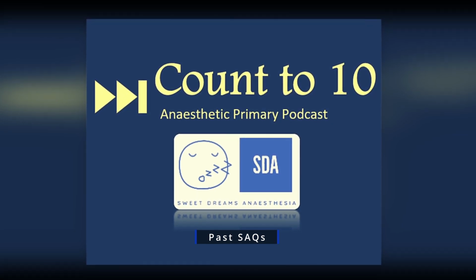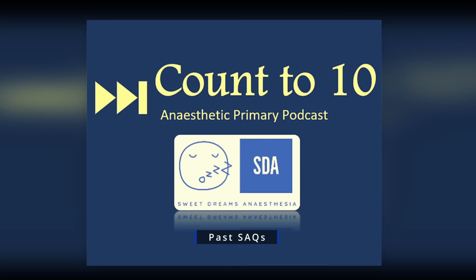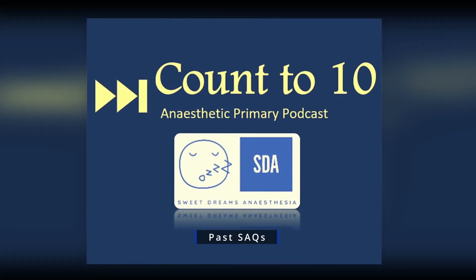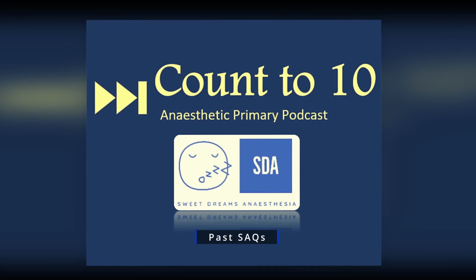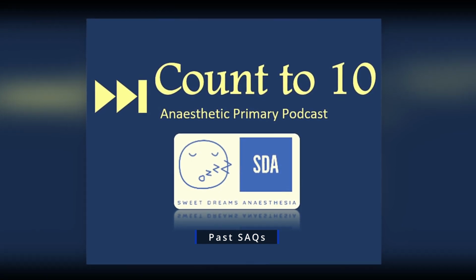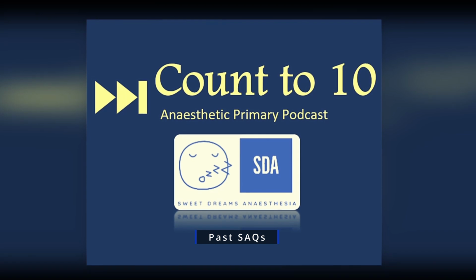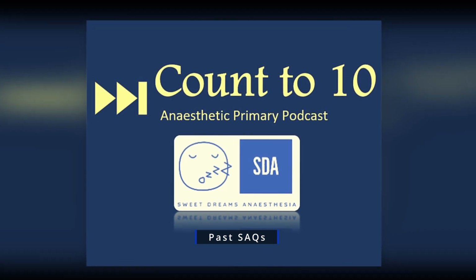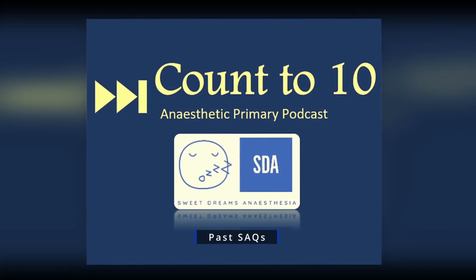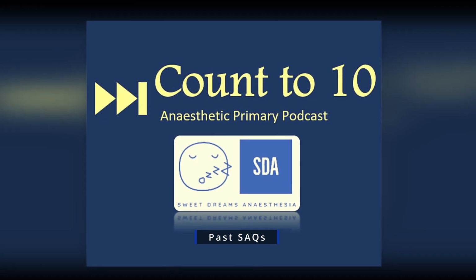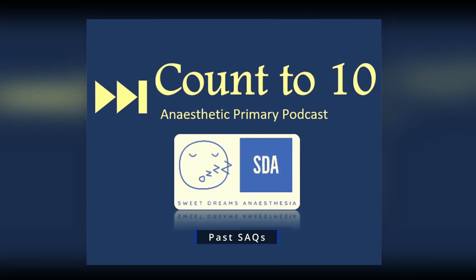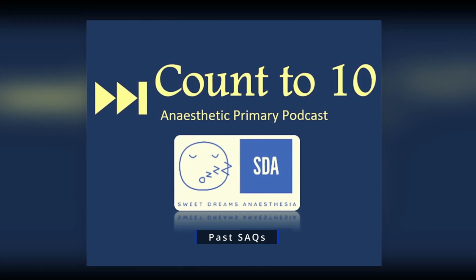The way oscillometry works, to quickly recap, is it starts off with the cuff being inflated above the patient's systolic blood pressure, and this is normally 20 to 30 millimeters above this threshold, and then the cuff is slowly released at 3 millimeters of mercury per second. Pulsatile flow is then detected through the cuff as it becomes partially decompressed, and this pulsatile pressure creates oscillations. These oscillations have varying amplitudes, and these oscillations and amplitudes are detected by the strain gauge.